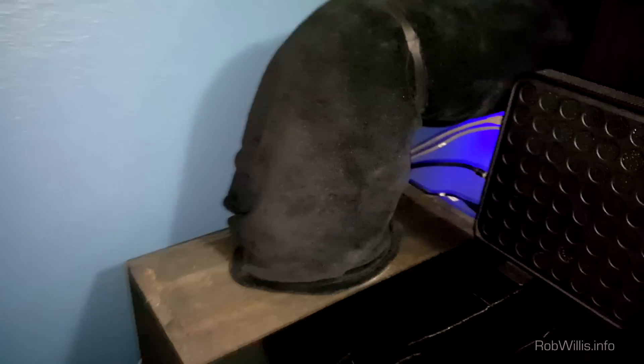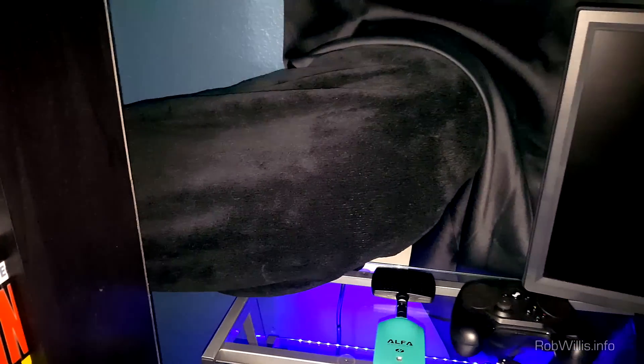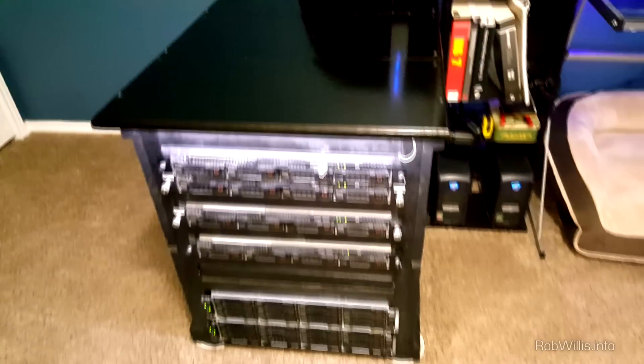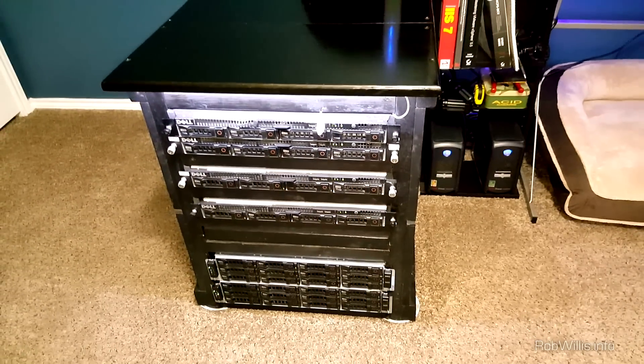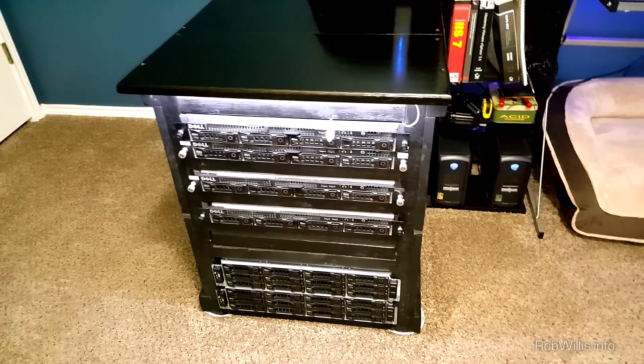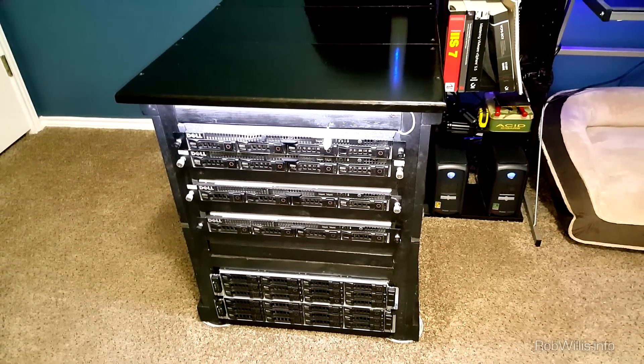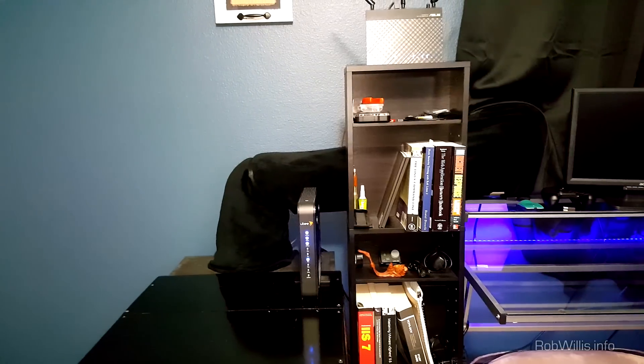I have one of those inside there, then there's a 6-inch flexible pipe that runs through the window and the whole thing's been wrapped in a blanket to kind of insulate it and keep the heat in as well as mask the whole thing. At the window I have a board with another 6-inch duct with another 6-inch fan mounted within there, and that one I have on an on and off switch so I can turn it on and off. It basically just directly exhausts all the heat from the servers directly out the window so it doesn't heat up the room.